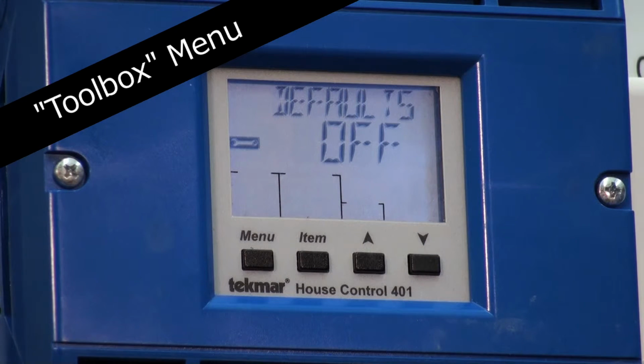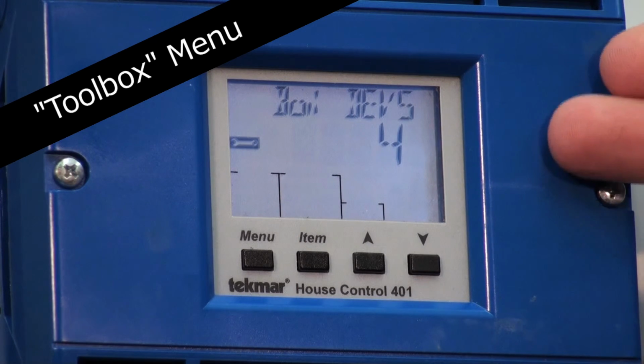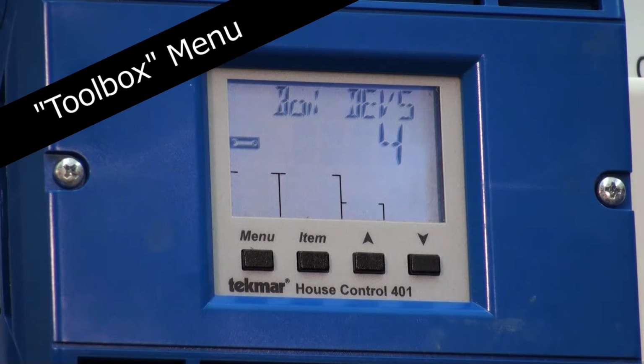And defaults is off. Defaults is factory defaults. If for any reason you wanted to set it back to where it came from the factory, you'd turn that on. After a few seconds, it'll go back to all factory defaults. Boiler devices, it's telling us how many thermostats we have on this control. And as you can see, devices 4 are 4 thermostats. It's reading all of them. And one way to know if it's reading, when you look at the thermostats, you see 2 arrows going in different directions. That means it's communicating with our control.